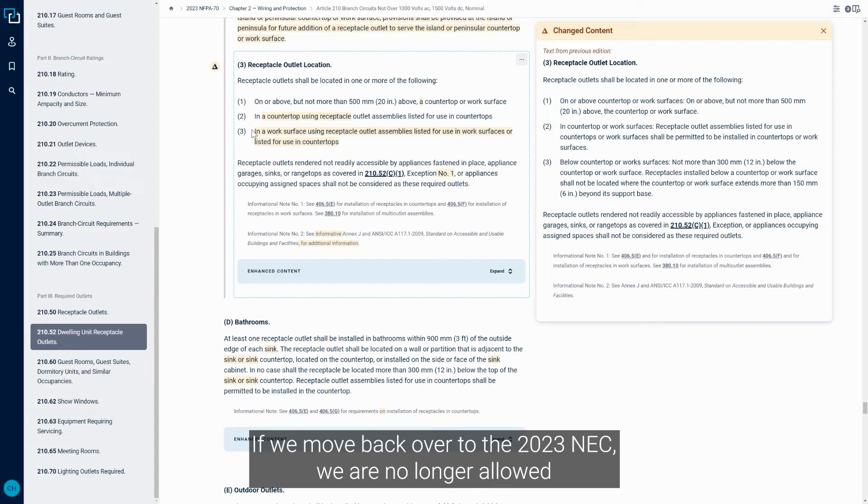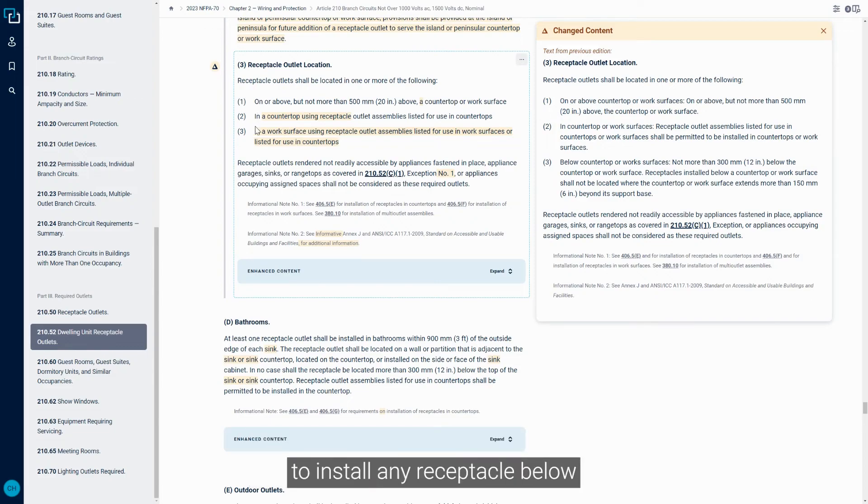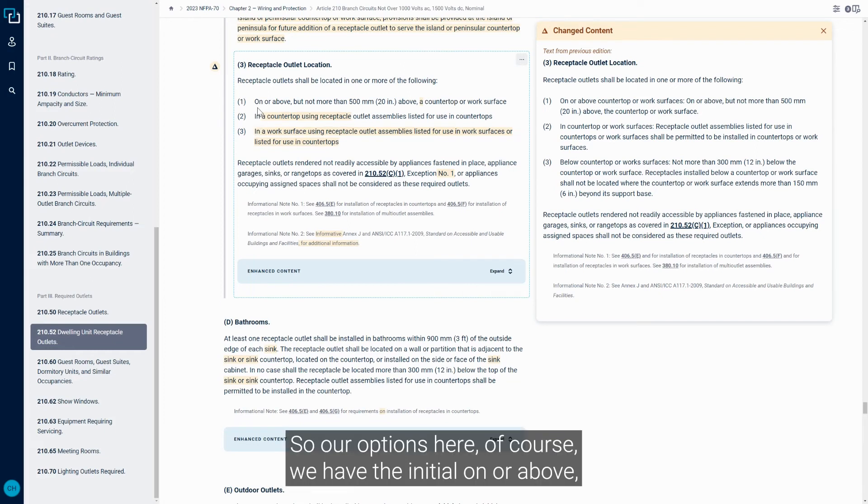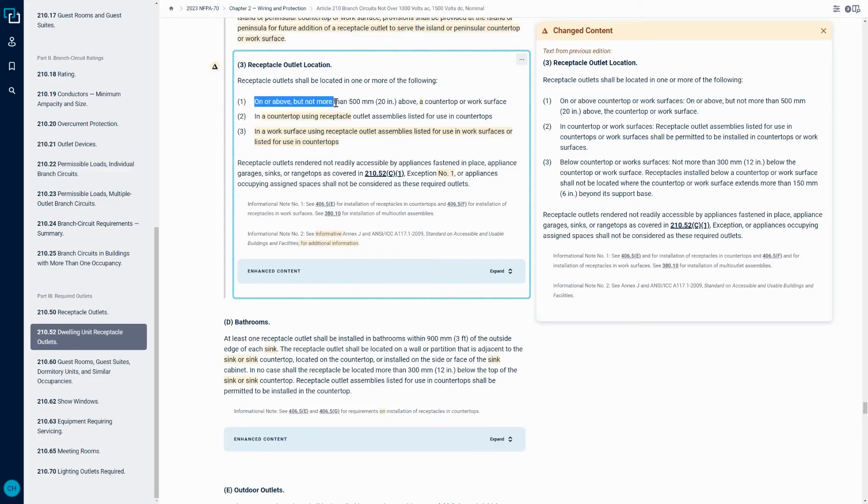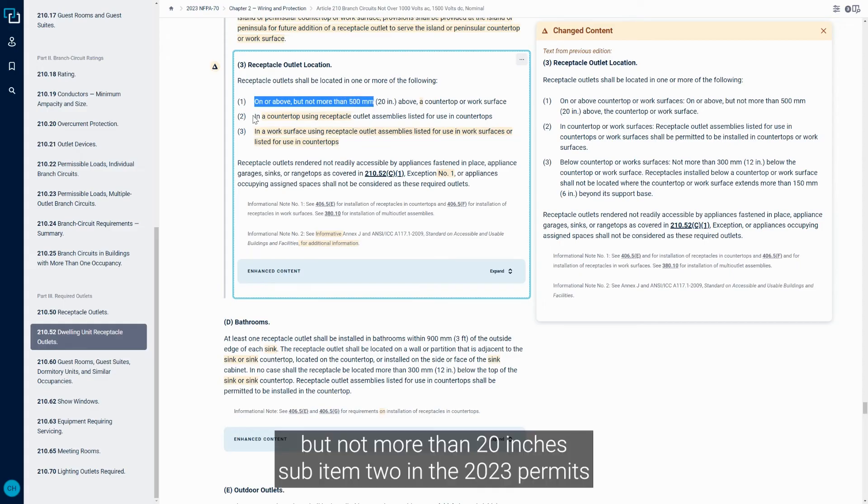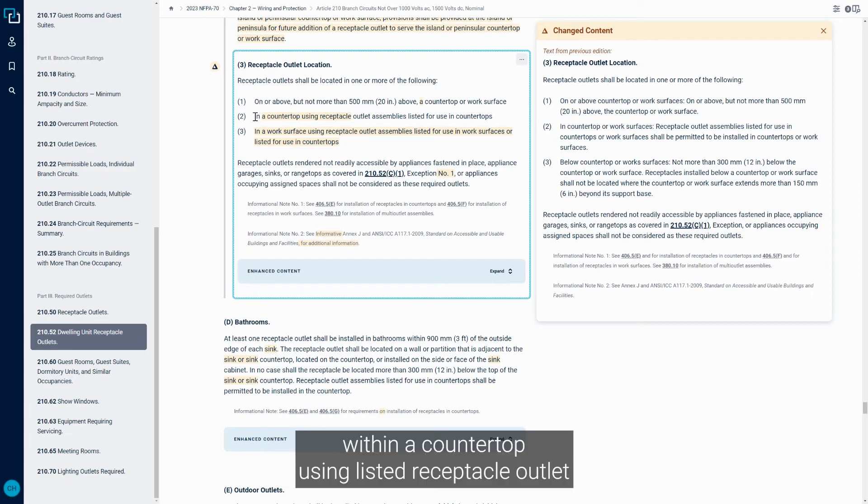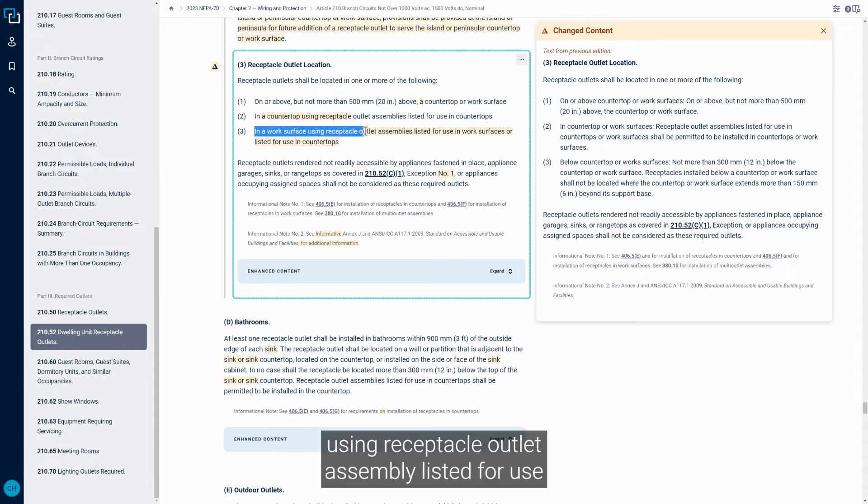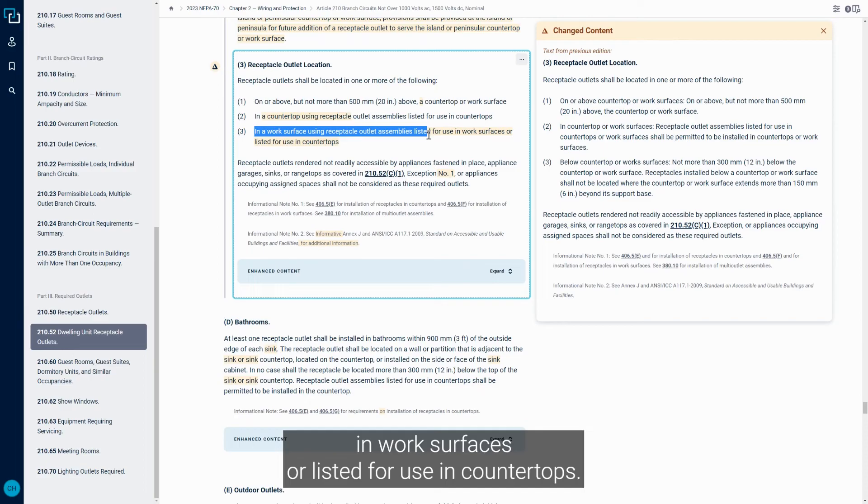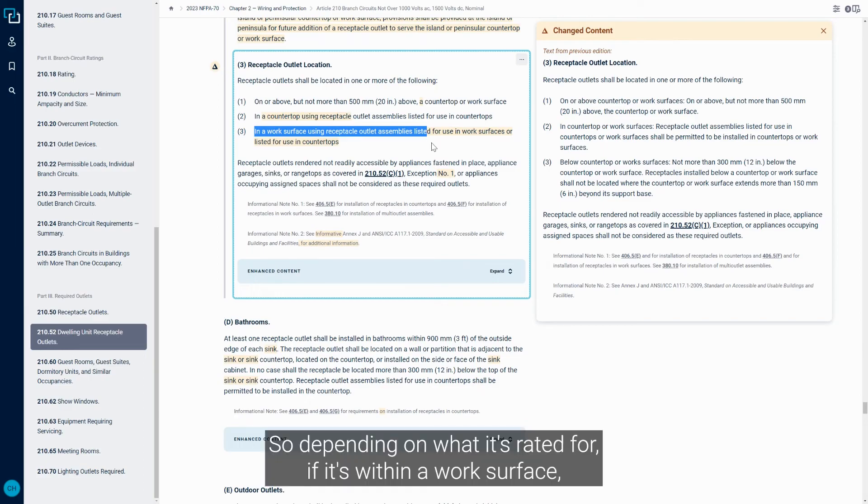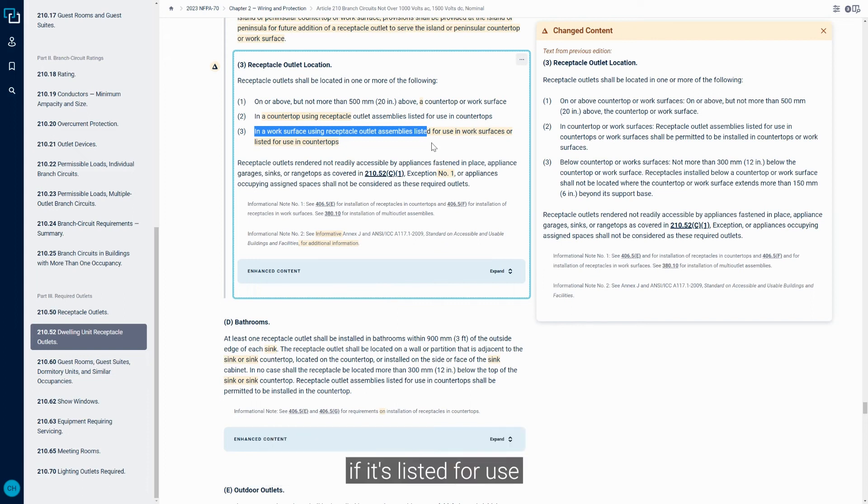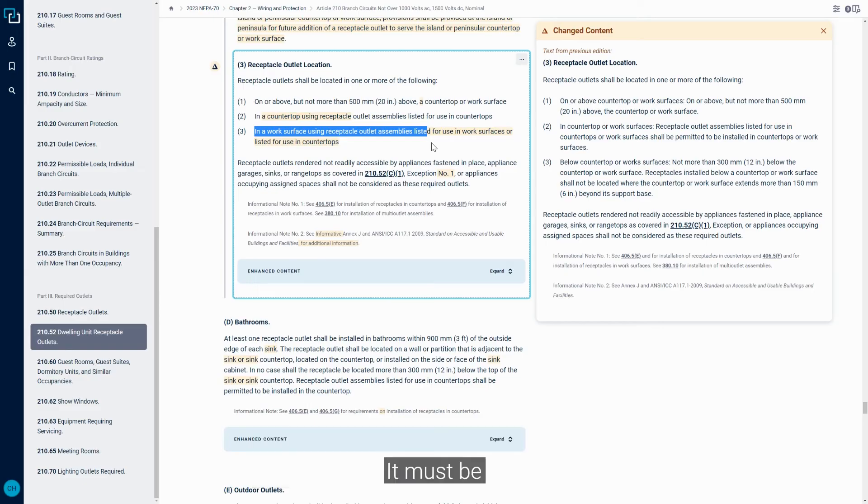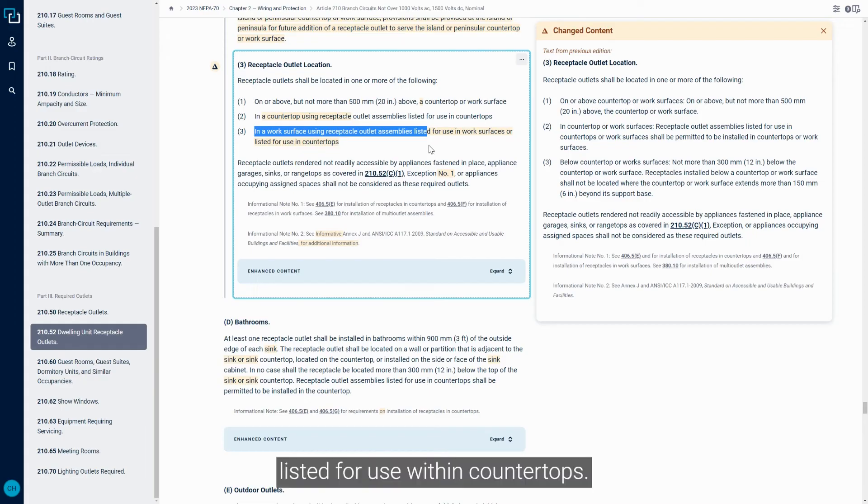If we move back over to the 2023 NEC, we are no longer allowed to install any receptacle below the countertop or work surface level. So our options here, of course, we have the initial on or above but not more than 20 inches. Sub-item two in the 2023 permits within a countertop using listed Receptacle Outlet Assembly for use in countertops. And then also three is in a work surface using Receptacle Outlet Assembly listed for use in work surfaces or listed for use in countertops. So depending on what it's rated for, if it's within a work surface, if it's listed for use within a work surface or a countertop, it can be utilized. Within a countertop, it must be listed for use within countertops.